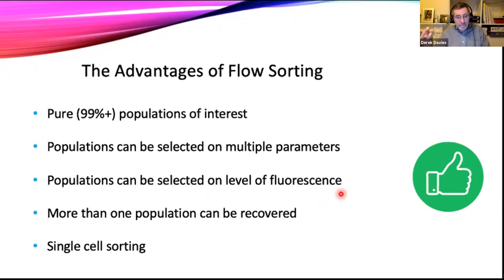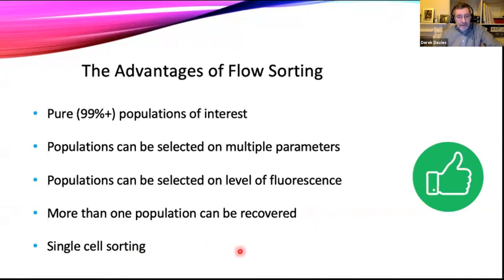We can also sort populations by level of fluorescence, which is something you can't really do with magnetic beads. For example, we could sort bright GFP from intermediate, low, or negative GFP. We can sort more than one population at once — pretty much every cell sorter on the market will allow us to do two populations; most will do four; some will do six at once. And importantly, we can do single cell sorting, which has become a major growth area for post-sort genomics, proteomics, or transcriptomics.